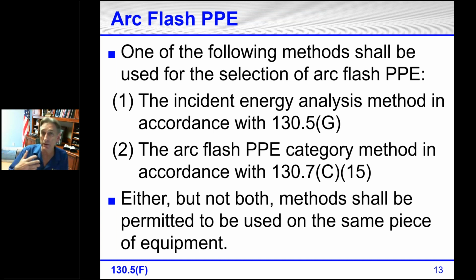So category 2 for arc flash does not mean you need test equipment or a voltage detector that is at least category 2 rated. They have nothing to do with each other. They just happen to be called categories. They are abbreviated CAT. There are 4 of them. We'll look at some of the ratings for the 4 categories for PPE. On your label, in fact, it says either can be done, but not both methods shall be permitted to be used on the same piece of equipment.